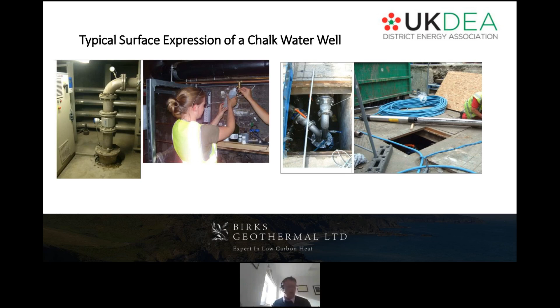Okay, moving to the crux then, which is the economics behind choosing water source over an air source. I'm going to start with the extra over CapEx. For the water source heat pump system, the borehole infrastructure at Colchester Gateway costs around £700,000. So per megawatt, I'd say a typical extra over capital cost for a well field is of the order of £500,000 to £1 million.